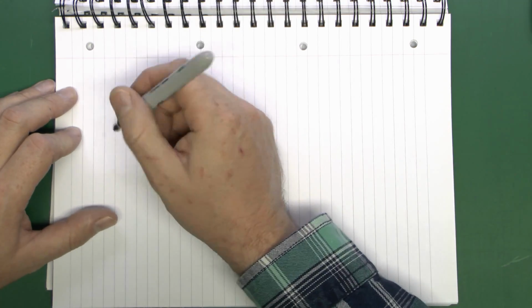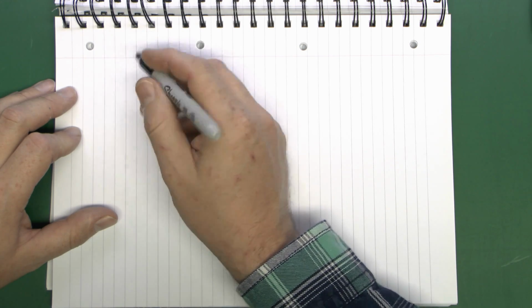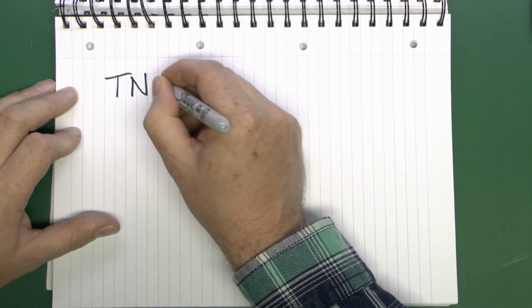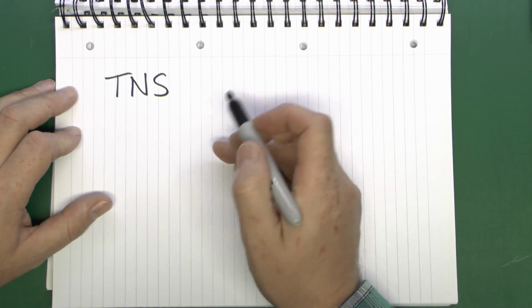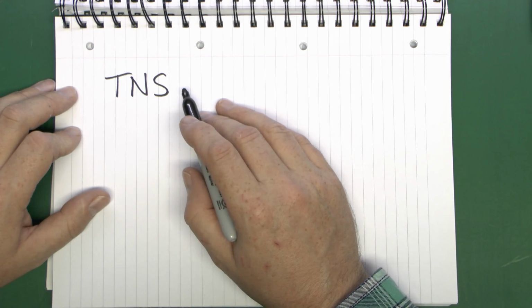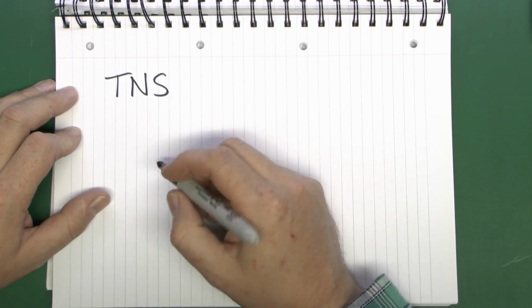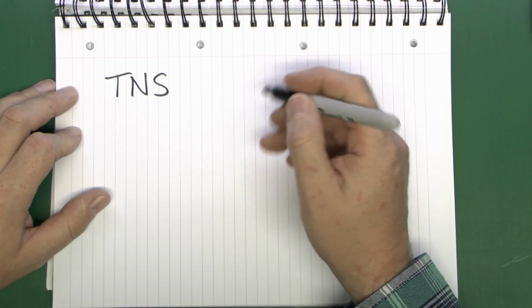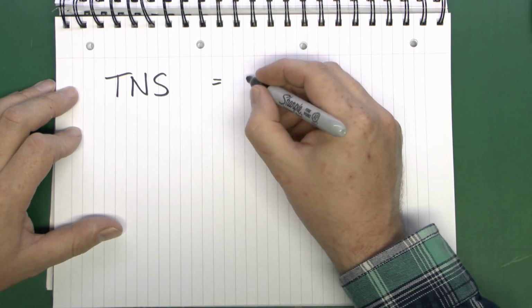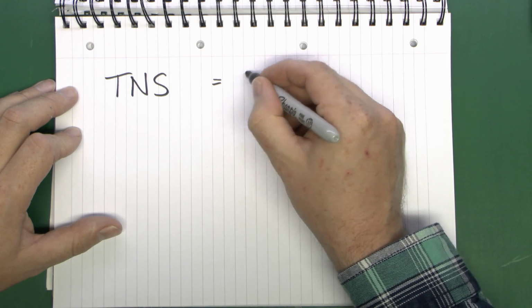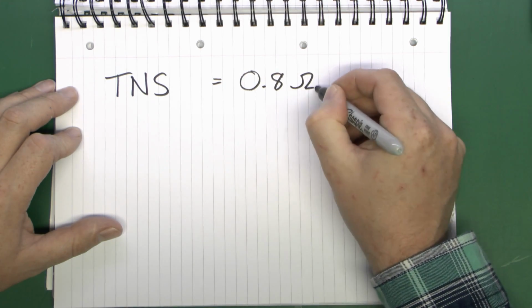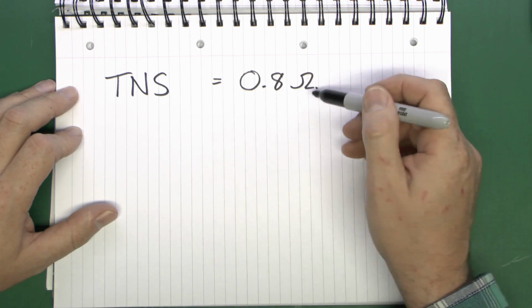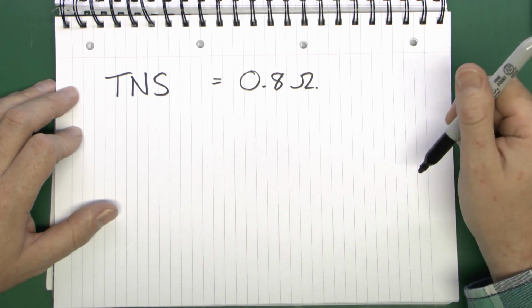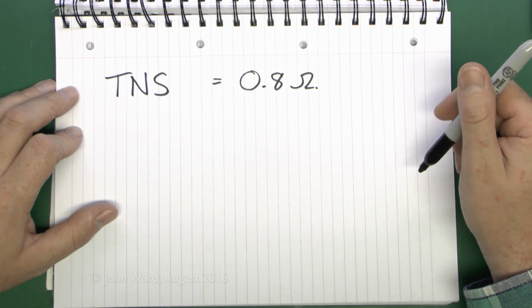Now, typical values for the external loop impedance depend on the type of supply that you've actually got. So we've seen these in a previous video, so I won't go over those in too much detail here, but there are essentially three main types used in the UK. You've got TNS, which is where the earth conductor from the transformer is a separate wire, hence the S here. So you've got your three wires coming in, line, neutral and earth. And in this case, a typical impedance between the line and earth would be anything up to around 0.8 ohms. Again, that's a kind of a maximum value. It could easily be considerably less than that, but anything up to that would be considered perfectly normal and acceptable.